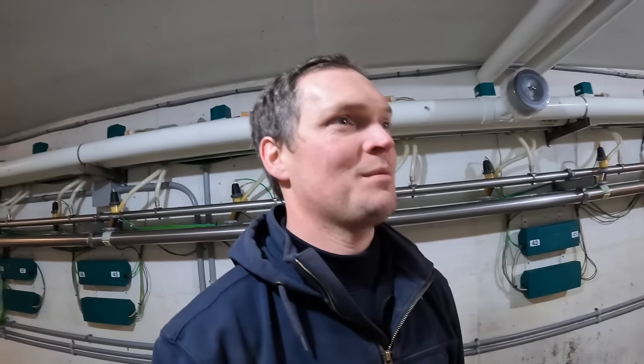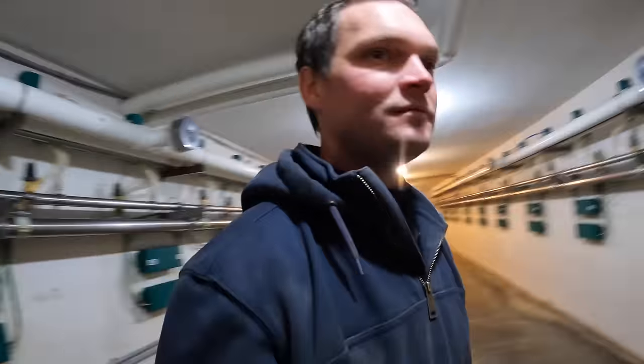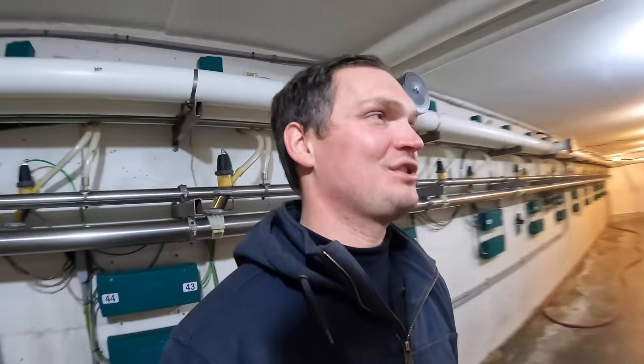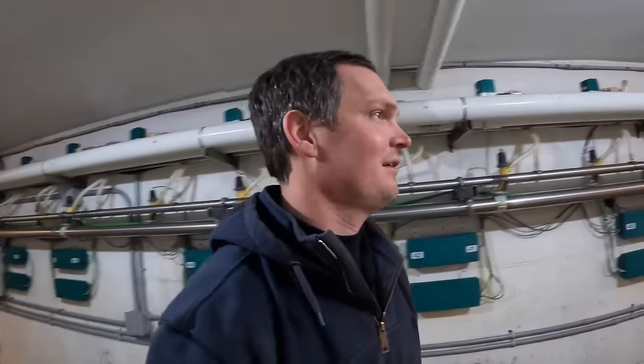I also noticed that I likely had picked the right loops because about a day after I turned those on, the floor was steaming at lunch when there wasn't water being sprayed in here, so it told me that that floor was warmer than it was before, so that was a good sign that we've got that working.